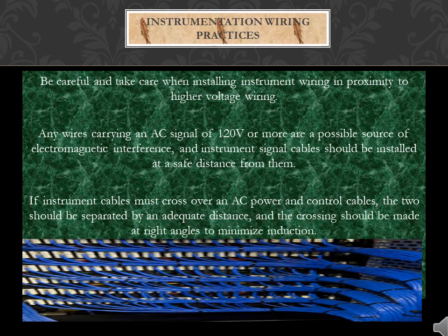Be careful when installing instrument wiring in proximity to higher voltage wiring. Any wires carrying an AC signal of 120V or more are a possible source of electromagnetic interference, and instrument signal cables should be installed at a safe distance from them. If instrument cables must cross over AC power and control cables, the two should be separated by an adequate distance and the crossing should be made at right angles to minimize induction.